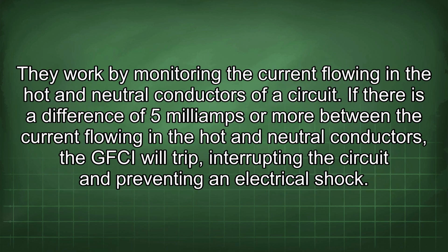They work by monitoring the current flowing in the hot and neutral conductors of a circuit. If there is a difference of 5 milliamps or more between the current flowing in the hot and neutral conductors, the GFCI will trip, interrupting the circuit and preventing an electrical shock.